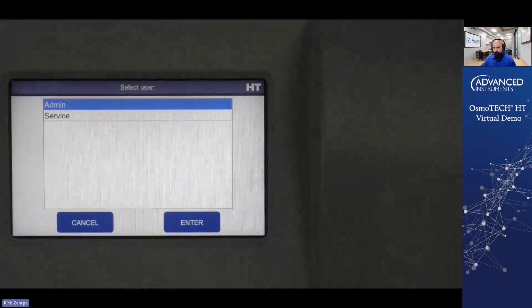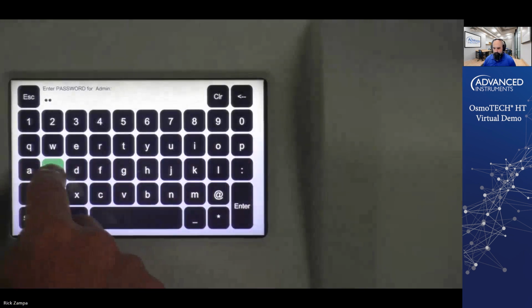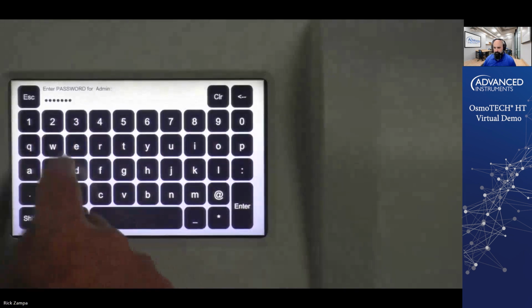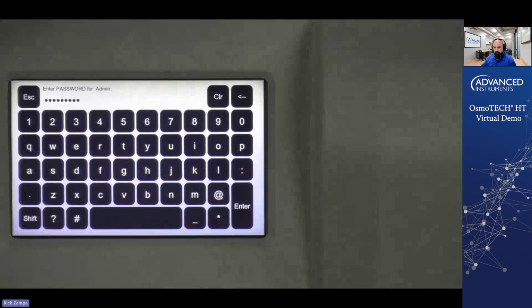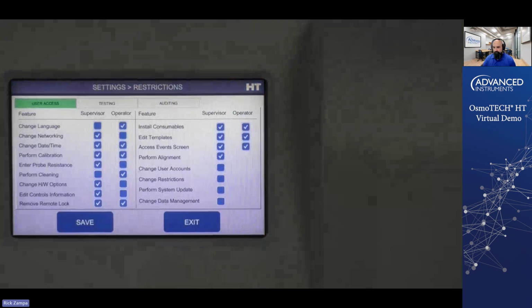So then we're going to go into restrictions. And restrictions is how you set up the testing capabilities on the instrument. As we were talking about earlier, you may want to have it set up so that you have to log in to run a test. You may want to require a sample ID. You may want to have people log in every time they run a test. Or maybe you just want a sample ID, or maybe you just want a user login.